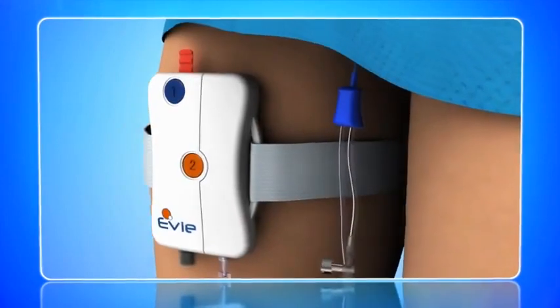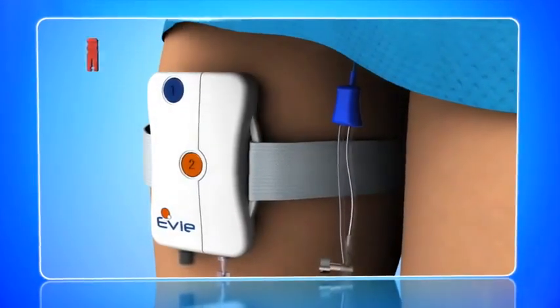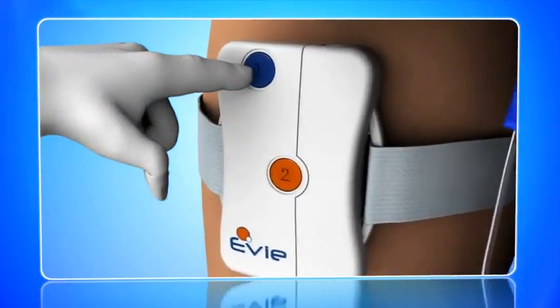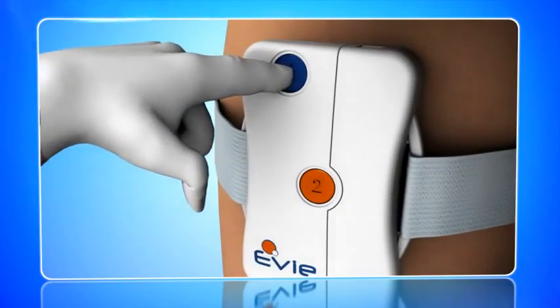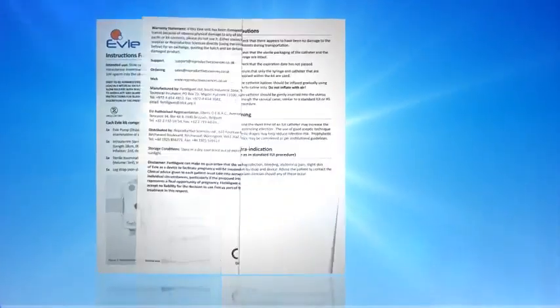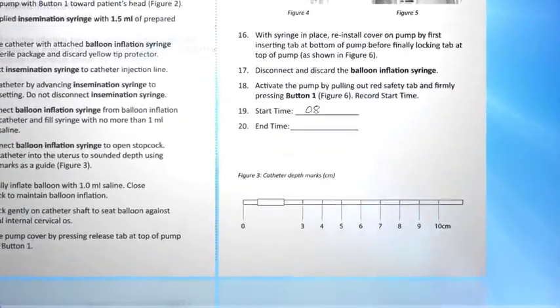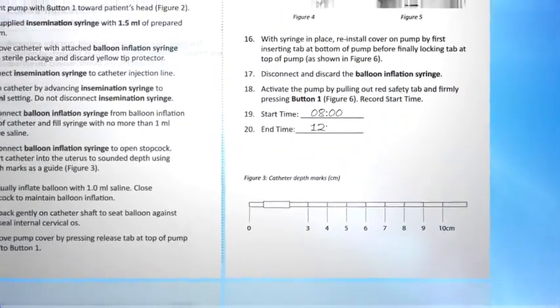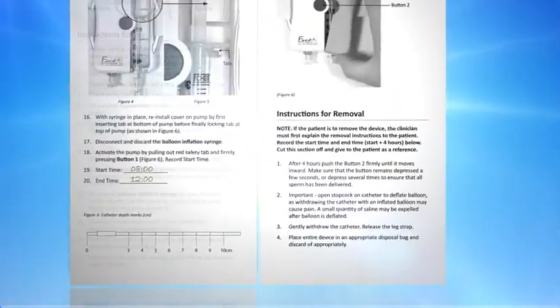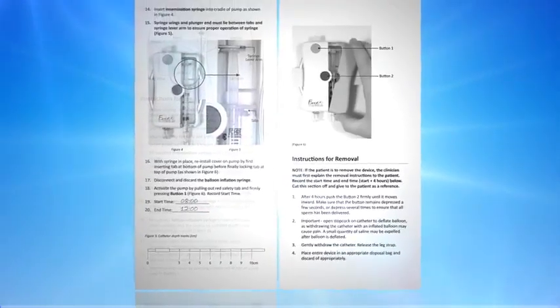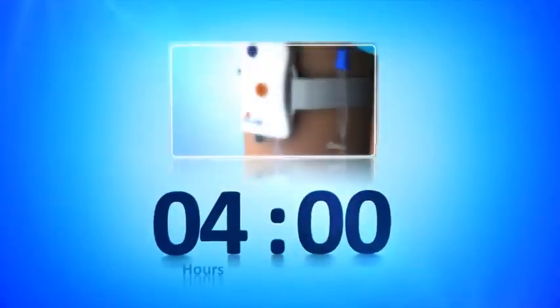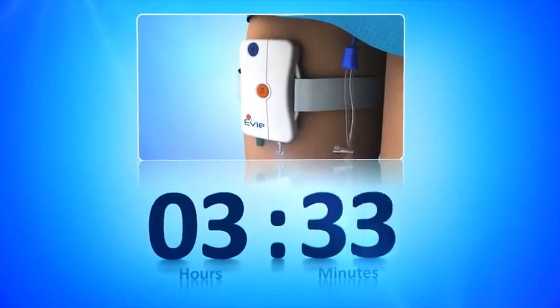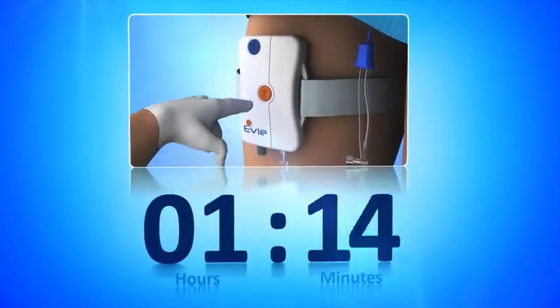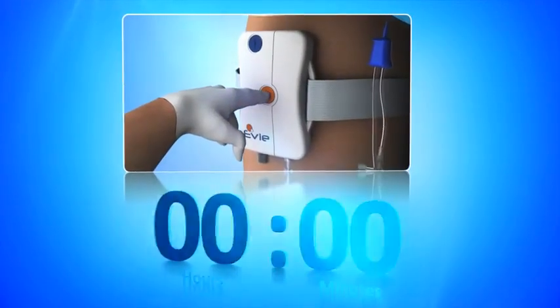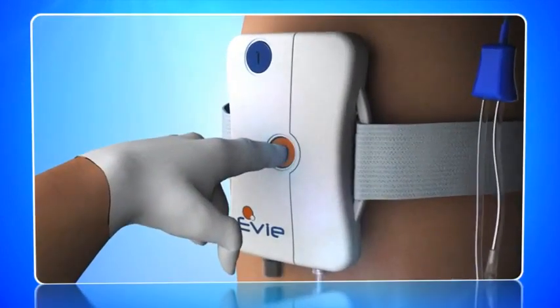Activate the device by pulling out the red safety tab and firmly pressing button number 1. Record the start time on the patient's instructions for removal and give to the patient. Instruct the patient to follow the removal guidelines as follows. After 4 hours, push button number 2 firmly until it moves inward. Make sure that the button remains depressed for a few seconds.